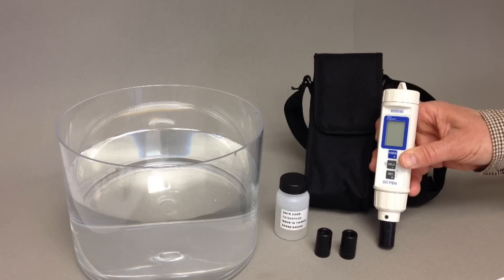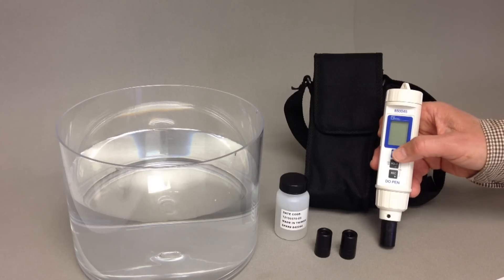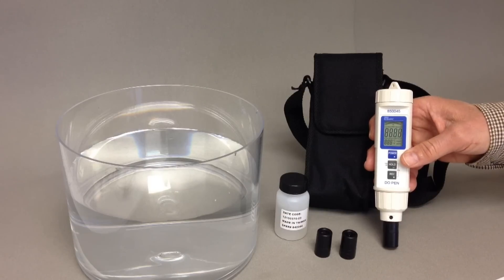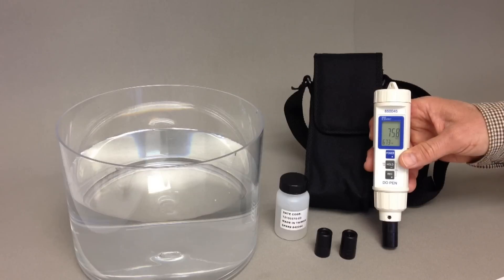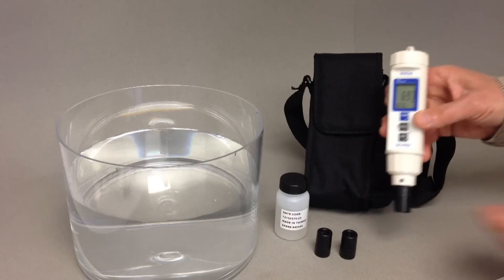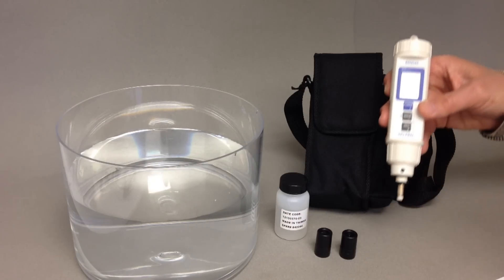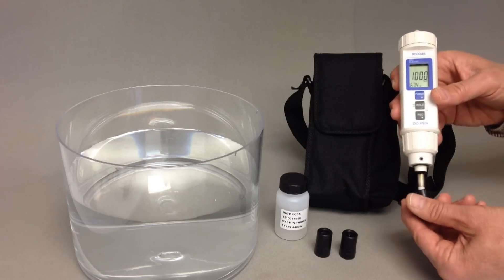Dissolved Oxygen Pen 850045 is easy to carry and sufficient for many surface dissolved oxygen measurements. The pen is designed for simple one-hand operation with automatic temperature compensation and easy calibration to air. The polarographic probe has a built-in temperature sensor and easy to replace pop-off heads.